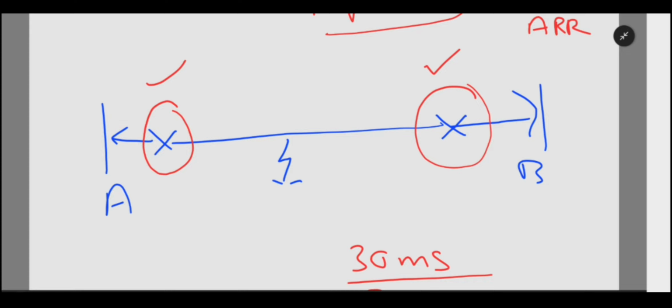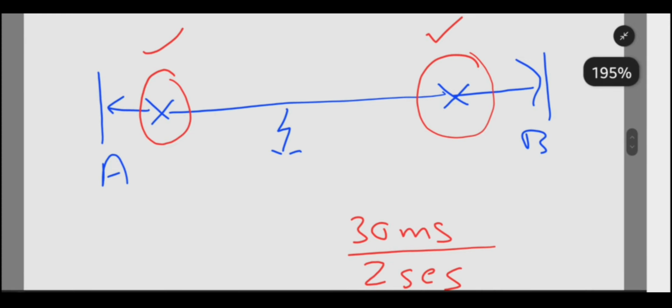If the fault again persists in the transmission line, that means it is 100% sure that the fault is the permanent type. So the breaker will open again and will not close, and will block the ARR and will not close the next times. Again, if the fault does not persist the second time, the breaker will remain in the closed position. So this is the function of the auto reclosure.